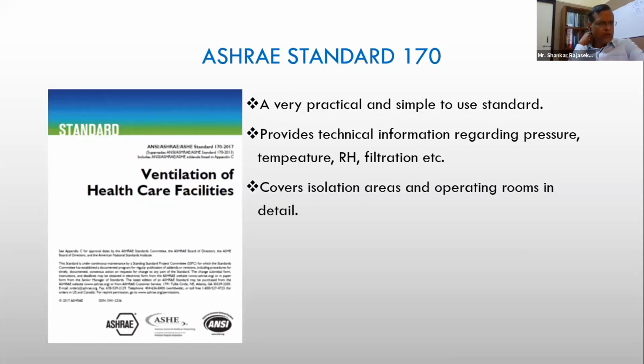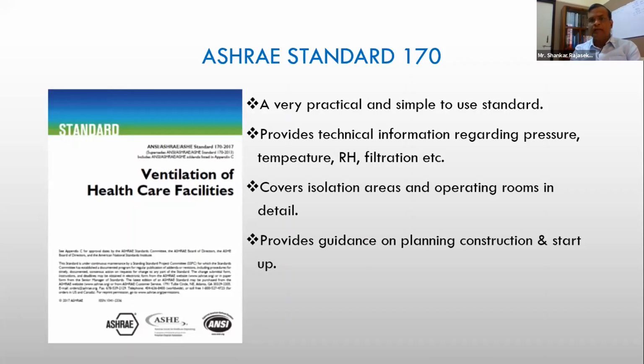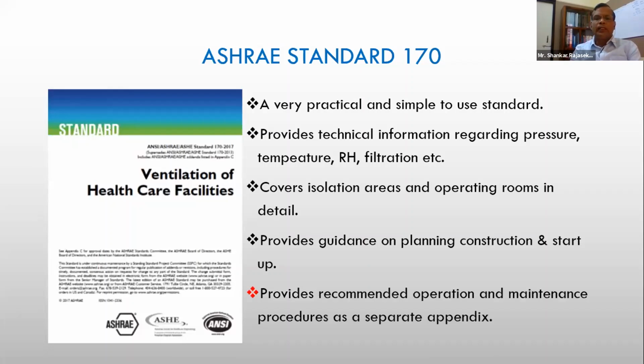But the ASHRAE standard provides it in a very simple and easy to understand manner. It covers isolation areas quite nicely. The standard comes along with another book called the ASHRAE handbook, the guidebook for healthcare facilities and clinics. I'm sharing some pictures from that book, where it clearly talks about how the supply and return air can be positioned in isolation areas. It provides guidance on planning, construction, and startup, and the recommended operation and maintenance procedures are given as a separate appendix.